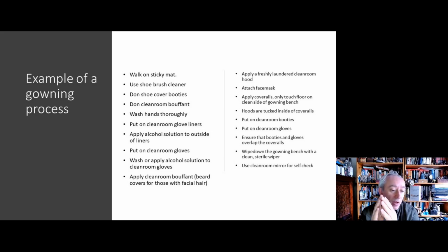And here we have special glove sprays for that purpose. Just on the subject of glove sprays, people sometimes ask, why do we have a different one for our bare hands compared to our gloved hands? Well, the one for the gloved hands is slightly more effective. That is 70% isopropyl alcohol, or IPA. However, if you apply that to bare hands, that will lead to dermatitis. So there's a fairly good one that's applied to bare hands, which is denatured ethanol, which contains emollients which will prevent the hands from drying out. So that's why there's that distinction.